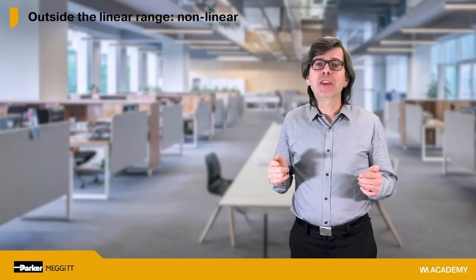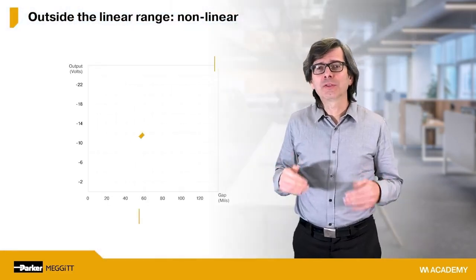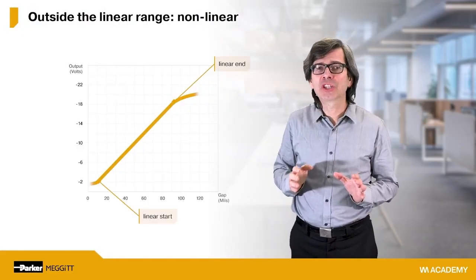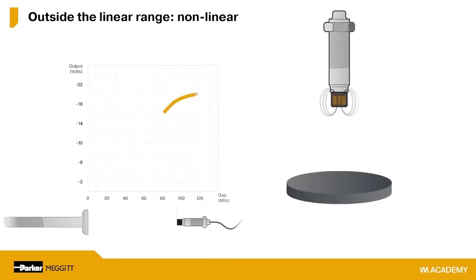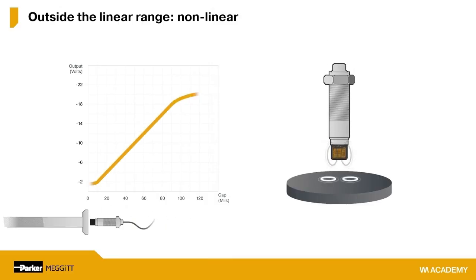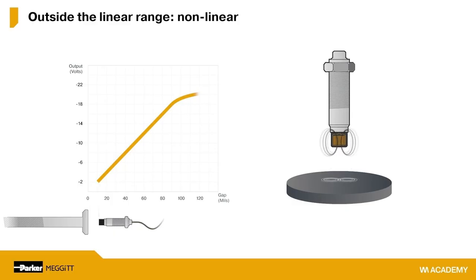Before we leave this topic, I want to make one additional observation. You may wonder why the response of the transducer becomes nonlinear outside of the linear range. If you remember the electromagnetic field emitted from the probe that we illustrated previously, you can easily imagine that if the probe tip is too close to the target, the maximum field is absorbed. So moving the target closer to the probe will not result in any additional field strength being absorbed. This is illustrated by the horizontal part of the yellow line below 10 mils. Placing a target closer than about 10 mils will not result in any change in voltage. It simply levels off at slightly below 2 volts.